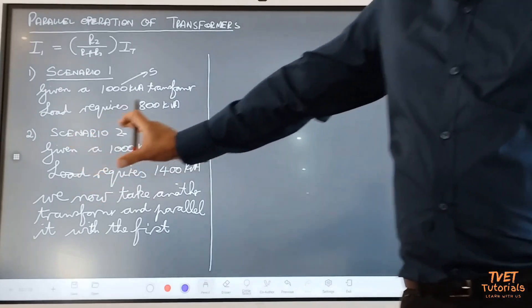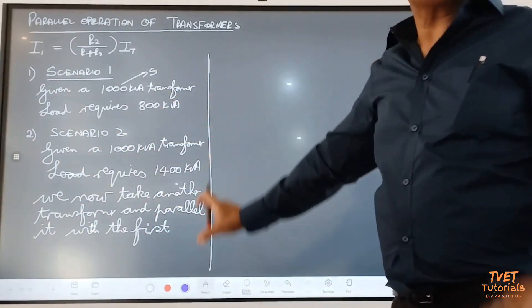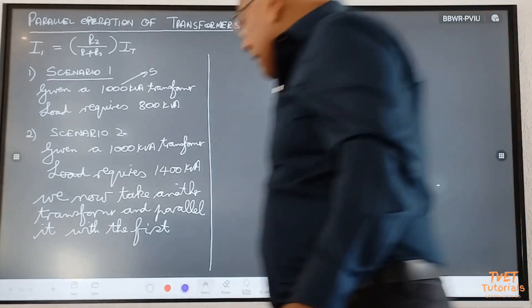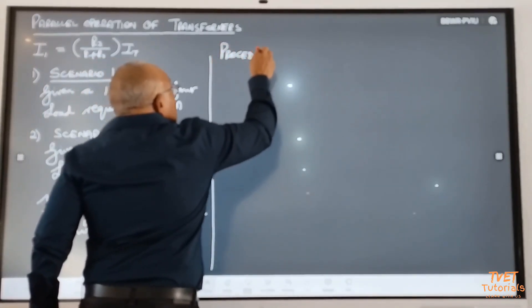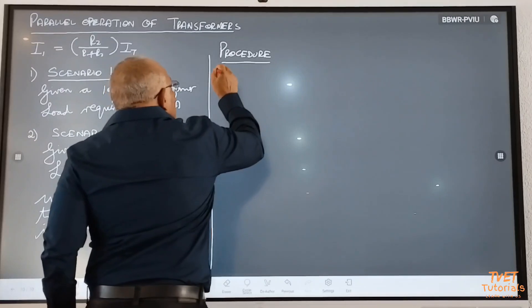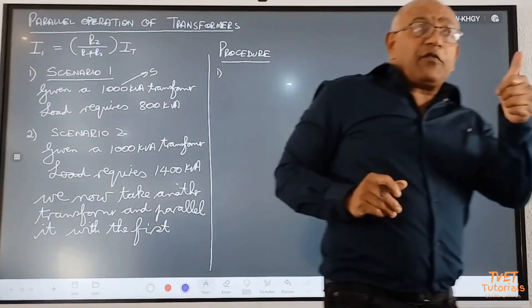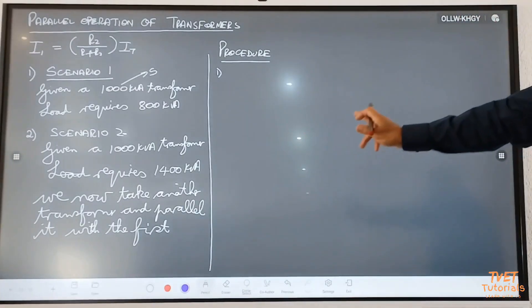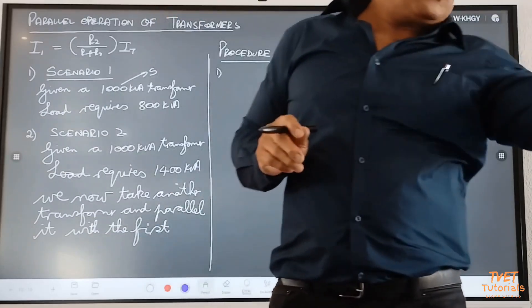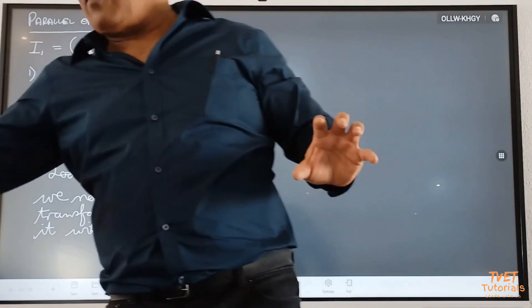You are going to start this lesson off by giving them the scenario. I didn't teach you all the parallel yet — I just showed you the scenario so the learner begins to understand what's going to happen. The procedure says step number one. One transformer is 1,000 kVA; what size is the other transformer? 500 kVA. I want to know how much of the total load transformer A will supply and how much transformer B will supply — it need not necessarily be equal.